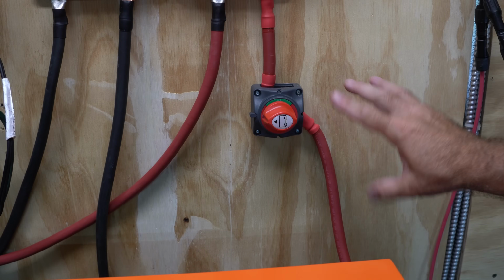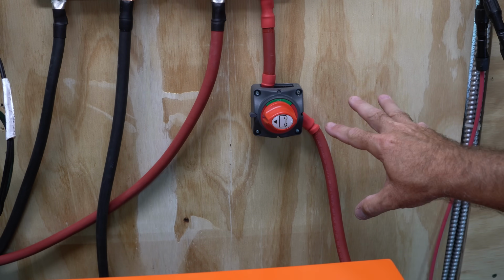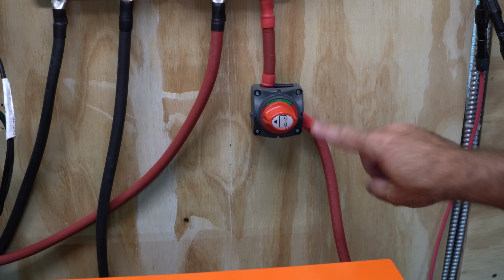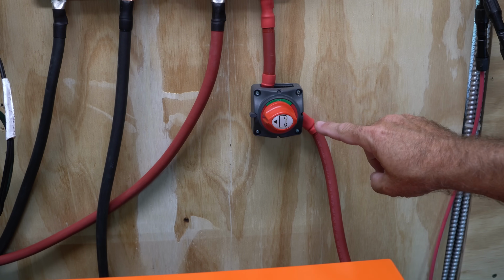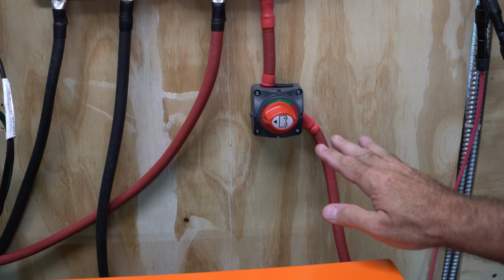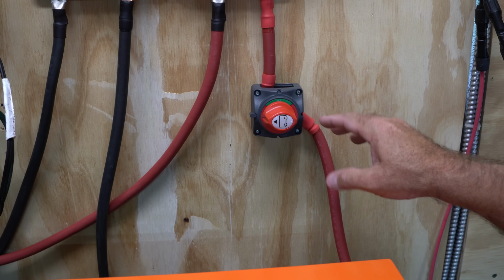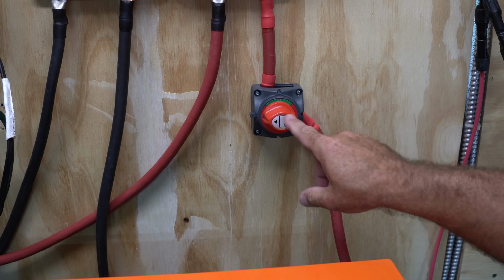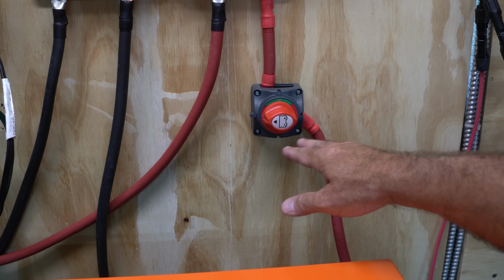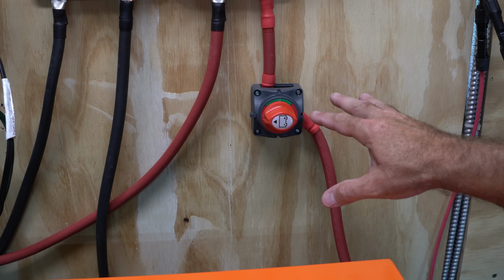It melted the plastic on this, and that is a very bad thing, because in the event that you overloaded this somehow, you would absolutely want the ability to disconnect power if you needed to. The fact that I melted this little handle here, that post in there, to the point where I can't turn it off from here, that's a problem.